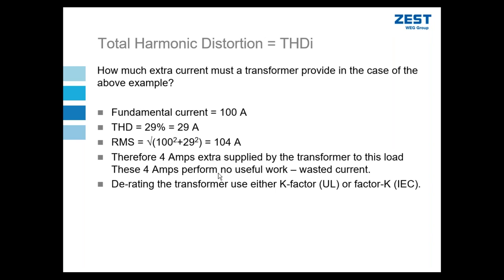All right, let's try to make this a little more practical. What does THDI mean for a plant designer? Well, that distorted current has an effect on certain equipment, for example, transformers. Transformers need to provide some additional current that does not do any work. It is simply used up by the harmonics of the distorted waveform. To look at an example using that same square wave example that we showed previously, let's take an example where our fundamental current is 100 amps. That would be the sinusoidal requirement for this transformer or this load. But I have a distorted waveform, and it has a total harmonic distortion of 29%. In this case, because my fundamental is 100, I can say that represents 29 amps out of the 100 amps.